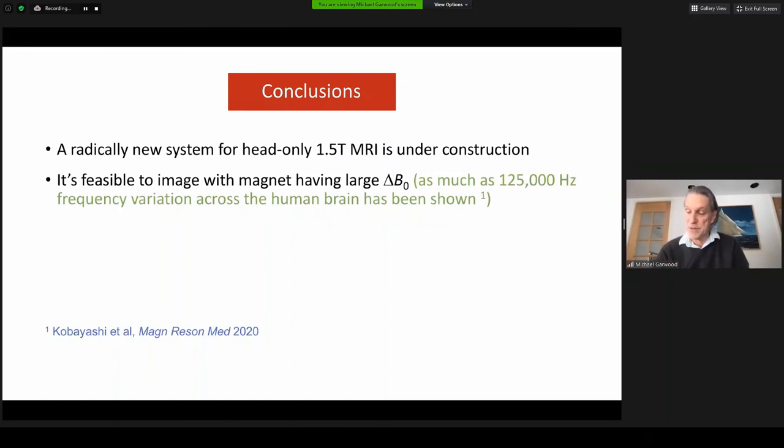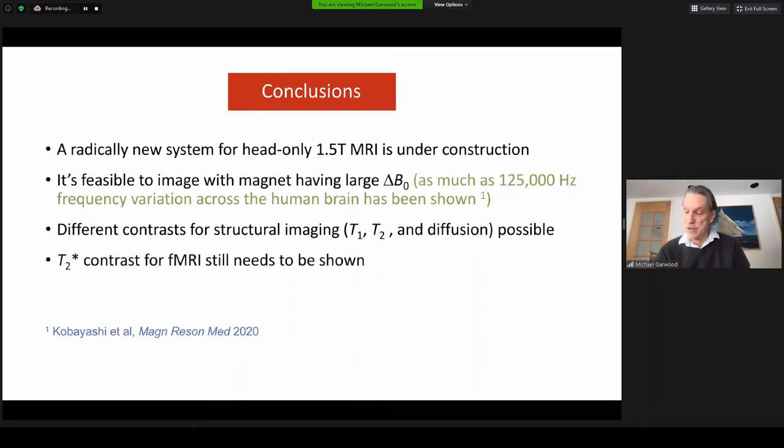In experiments, we have shown the feasibility to image with as much as 125 kilohertz of frequency variation across the brain. Furthermore, we have shown it's possible to generate different types of contrast, including T1, T2, and diffusion contrast. Although at this time, we still don't have a method to image with T2 star contrast, but we're working on that.